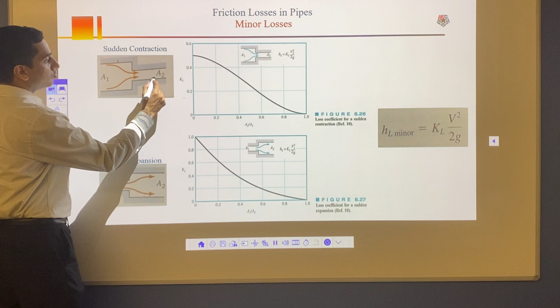So let's say that A2 by A1 comes around 0.4. If that's the case, then all you have to do is get that A2 by A1, draw a vertical. Wherever it will meet that black line, draw a horizontal from that black line. That should be your KL. Now in this case it comes around 0.3. Now let's say your A2 by A1 is 0.6. In that case, draw a vertical here, meet the black line here, draw a horizontal, and then it should come around 0.18, let's say. So that's how you can calculate the value of KL in case of sudden contraction.